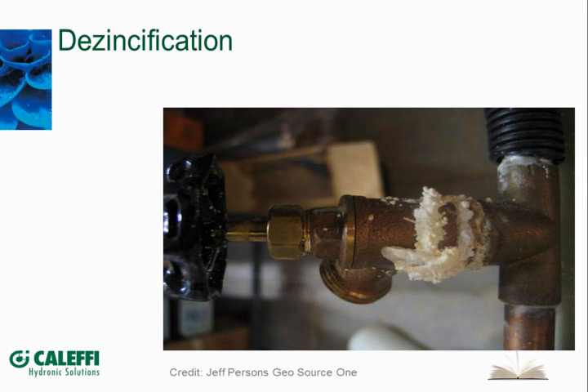Here's an issue you'll find occurs frequently with soft water: dezincification. You might remember from the galvanic series that zinc is very low on the series, and our brass contains copper and zinc. The water can aggressively go after that zinc, dissolve it from the brass, making the brass porous, and you start to find this white crust from the minerals in the softened water coming out through the brass valve.